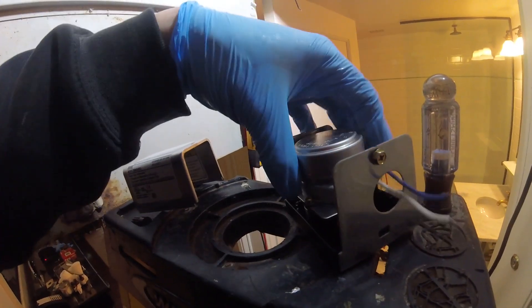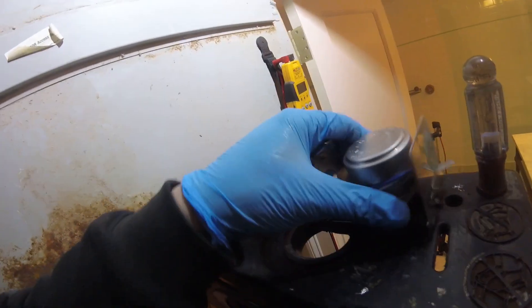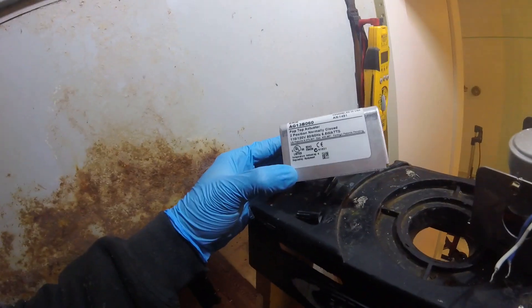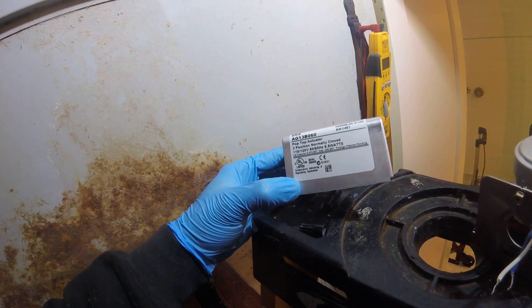So this is a pop top actuator. Just pull these. This can pop right off the valve. So this thing needs to be replaced. Let's see, this is a 120 volt valve. Two position.